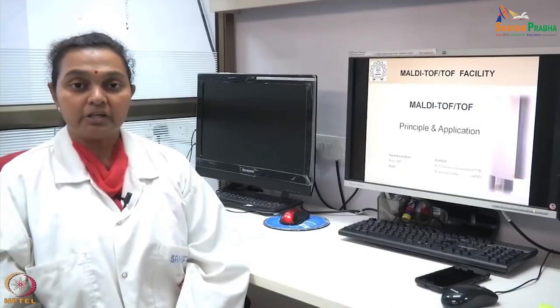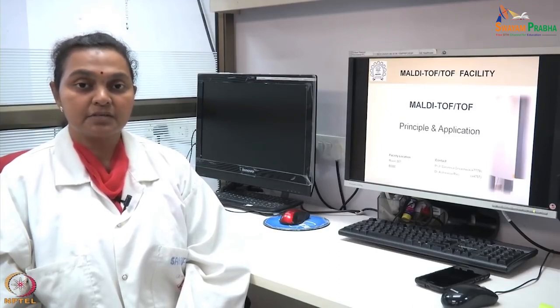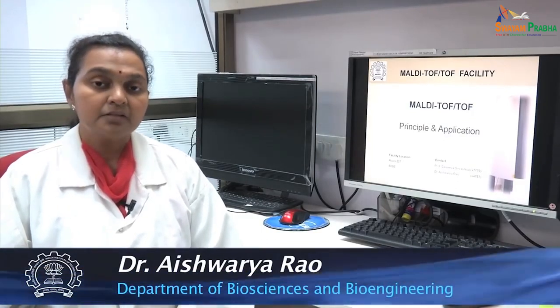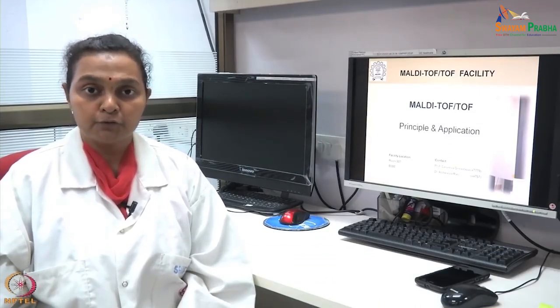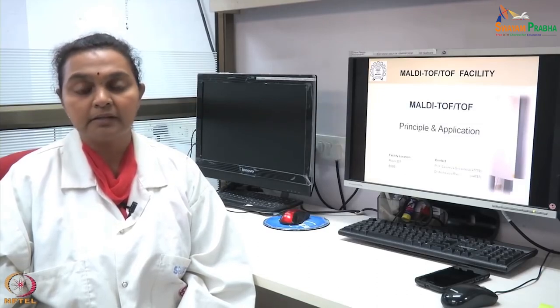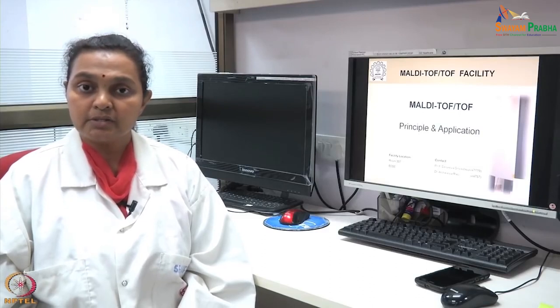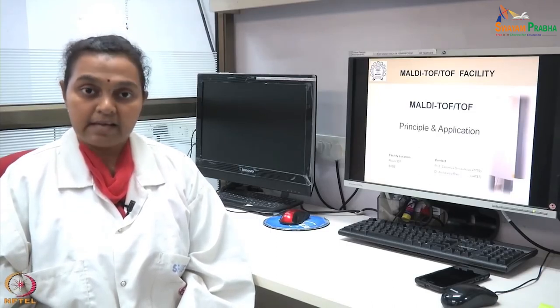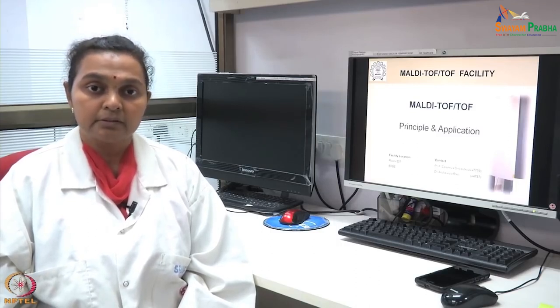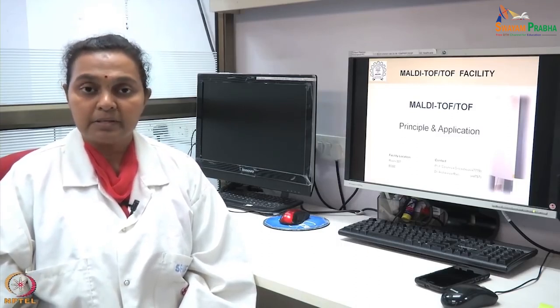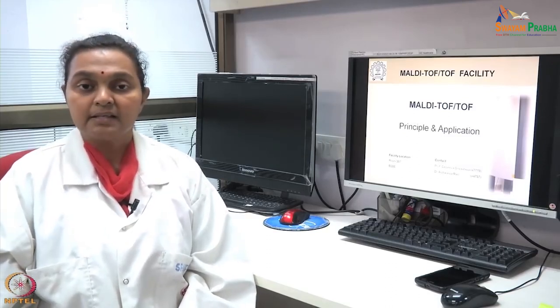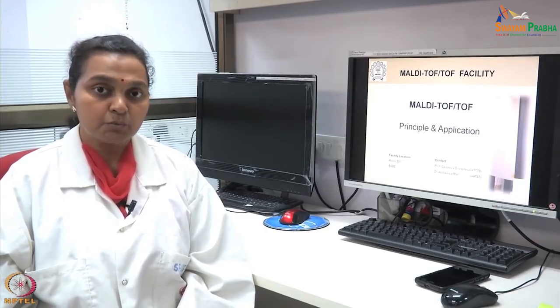Let us start the first demonstration on MALDI-TOF-TOF. I am Dr. Aishwarya Rao, in charge of the MALDI facility in Professor Sanjeeva Srivastava's lab. MALDI is one instrument used as a mass spectrometer. The instrument behind me is a MALDI-TOF-TOF called the Autoflex Speed, made by Bruker. The ionization source in this instrument is a smart beam laser used to ionize the samples, and the mass analyzer is called the time-of-flight, and MALDI stands for Matrix Assisted Laser Desorption Ionization.